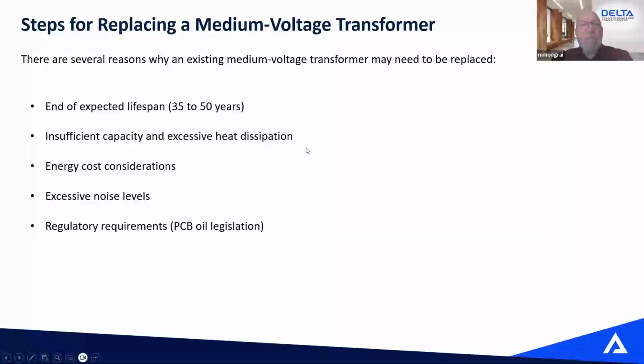Okay, here we are. Back in the 1960s and 70s, there was lots of construction going on across the country. When you put up a brand new building, it's easy to install a large medium voltage transformer. Usually it's going to be dropped in the basement and then we build the building around it, or it's brought onto a certain floor. In the room, we have lots of access because the building is under construction. But then, at the end of life, to replace those transformers, many times there are serious access problems or concerns.